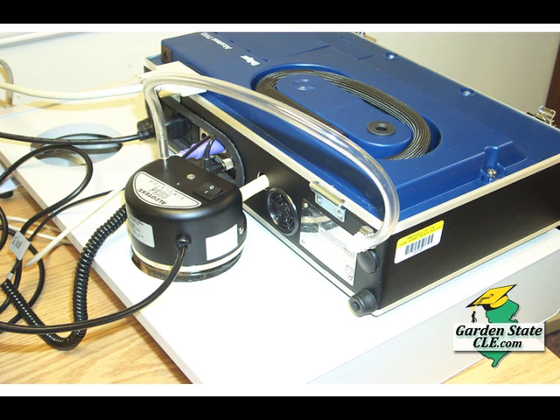There's a whole bunch of functions that they need, and it also opens up the ability to do the check of calibration functions. A regular trained operator can't do that. So the key is essentially a temperature probe that has a chip on it. When the business end of it is in the CU-34, and this goes in the back of the Alcotest, it opens up these administrative functions. It's like on your office computers. You may have administrator mode and user mode.